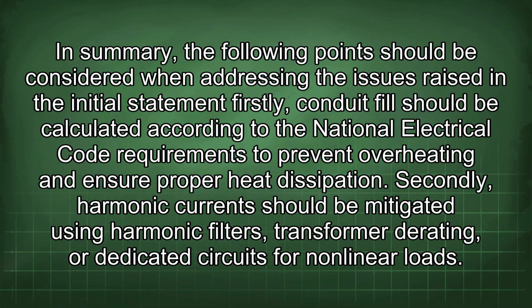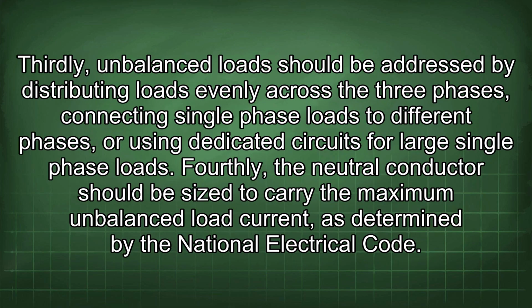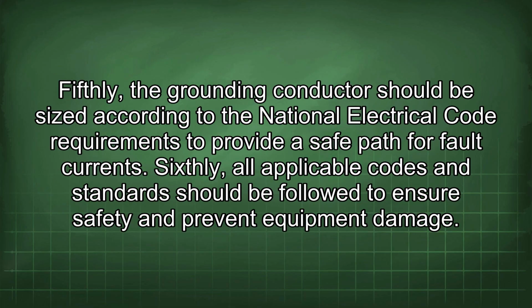Secondly, harmonic current should be mitigated using harmonic filters, transformer derating, or dedicated circuits for nonlinear loads. Thirdly, unbalanced loads should be addressed by distributing loads evenly across the three phases, connecting single-phase loads to different phases, or using dedicated circuits for large single-phase loads. Fourthly, the neutral conductor should be sized to carry the maximum unbalanced load current as determined by the National Electrical Code. Fifthly, the grounding conductor should be sized according to the National Electrical Code requirements to provide a safe path for fault currents.